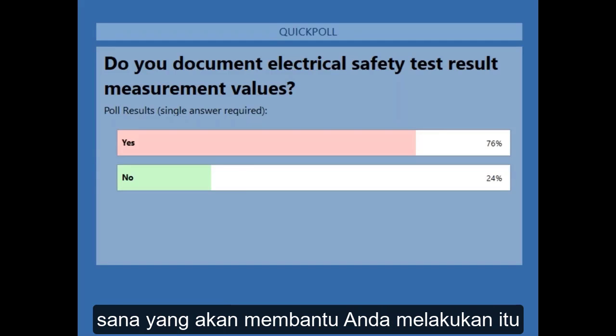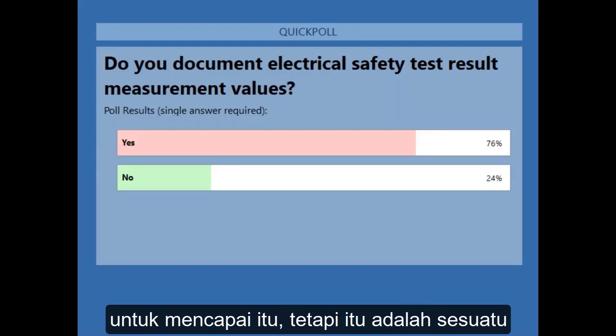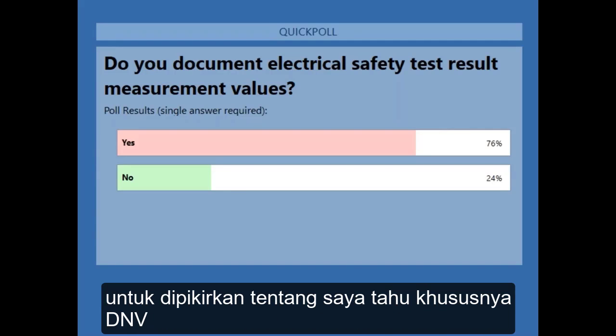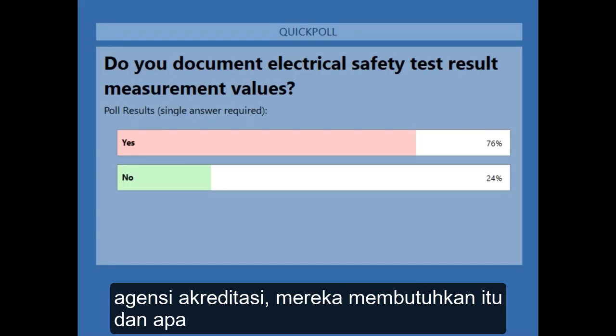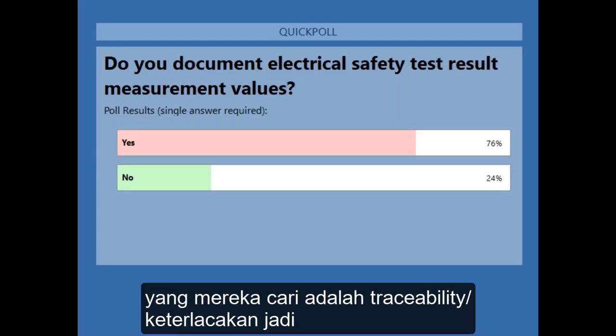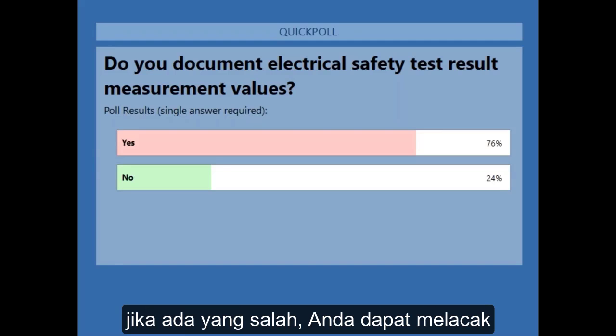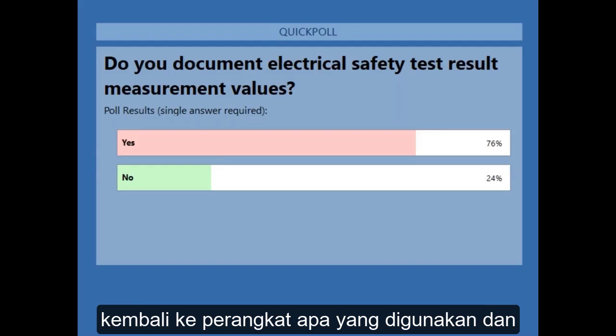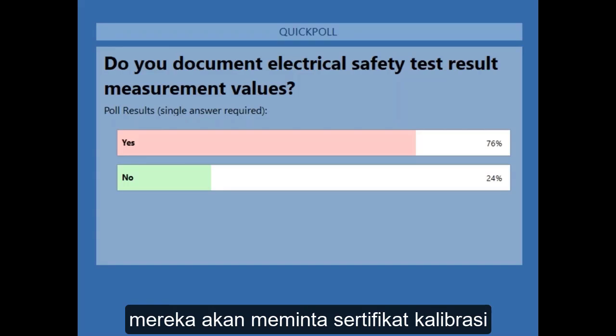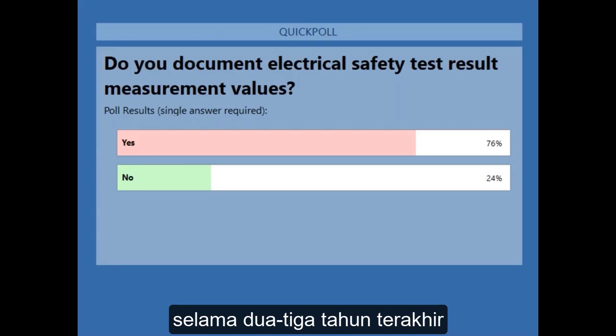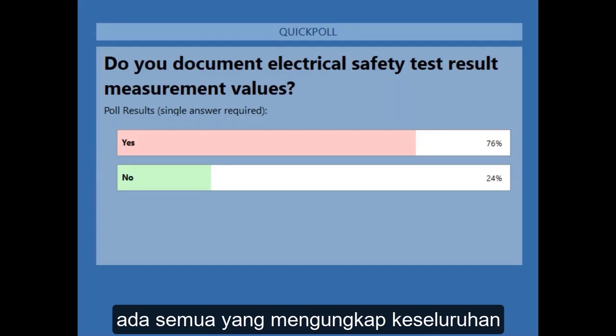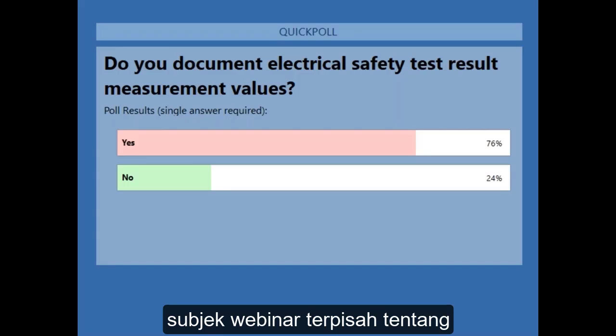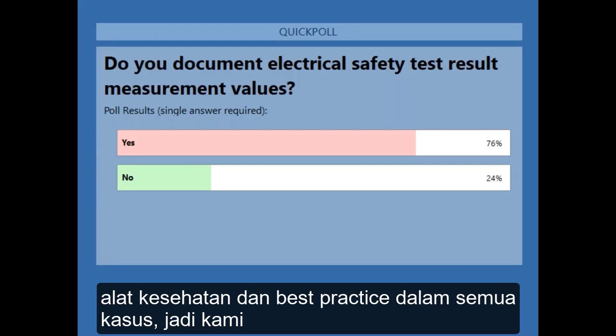Again, there's software out there that'll help you accomplish that, but that is something to think about. I know in particular DNV, which is one of the accreditation agencies, requires that, and what they're looking for is traceability. So if something does go wrong, you can trace it back to what devices were used, and they will ask for calibration certificates of your electrical safety analyzer for 2-3 years prior as well, and you can show them that traceability from your certificates. That uncovers a whole separate webinar subject about metrology for medical device quality assurance, and a best practice in any case.